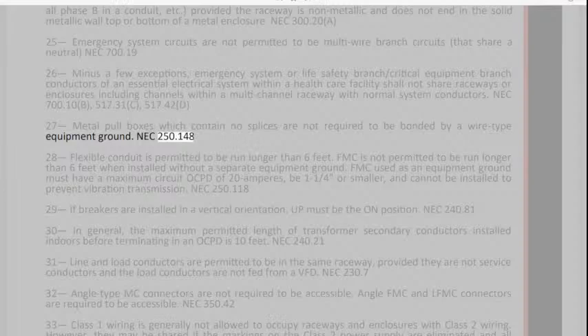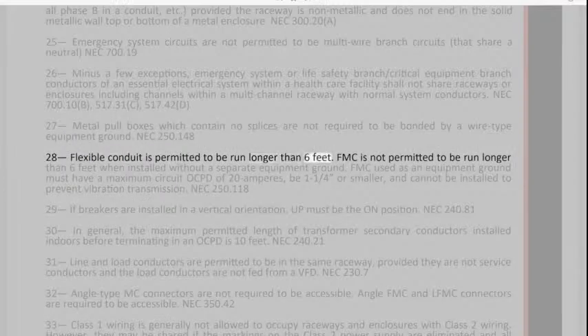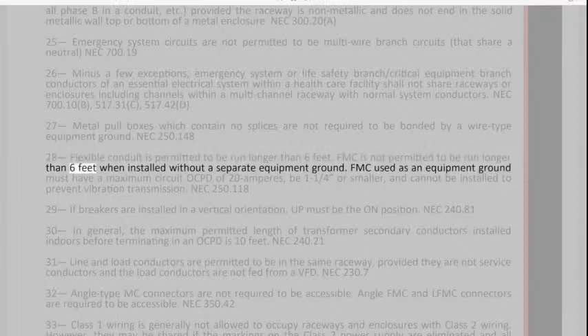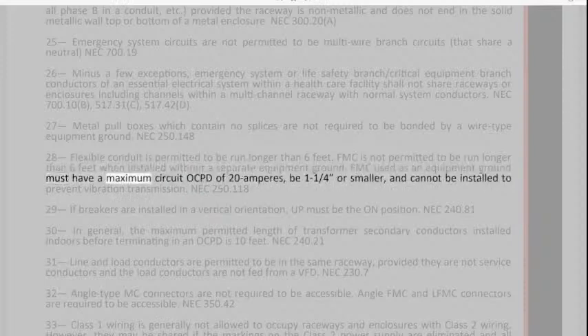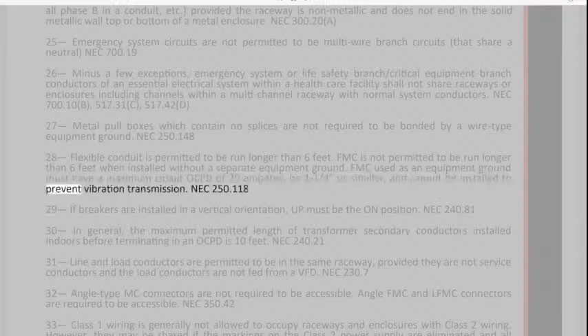250.148. 28. Flexible conduit is permitted to be run longer than 6 feet. FMC is not permitted to be run longer than 6 feet when installed without a separate equipment ground. FMC used as an equipment ground must have a maximum circuit OCPD of 20 amperes, be 1 1/4 or smaller, and cannot be installed to prevent vibration transmission.